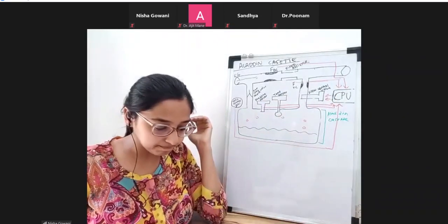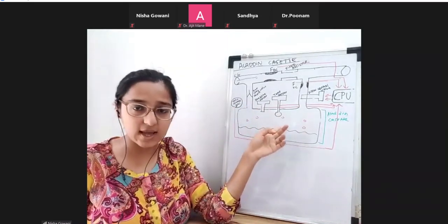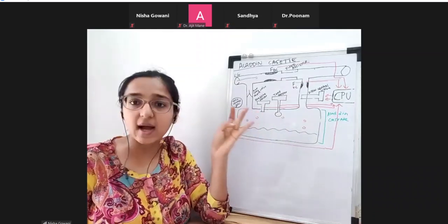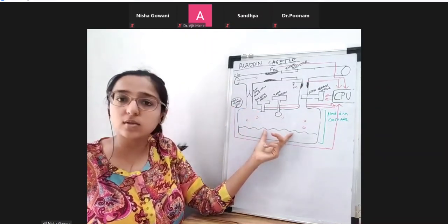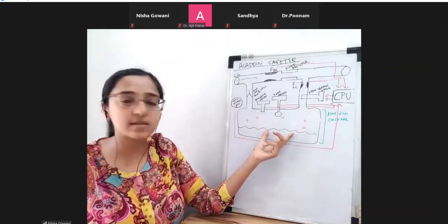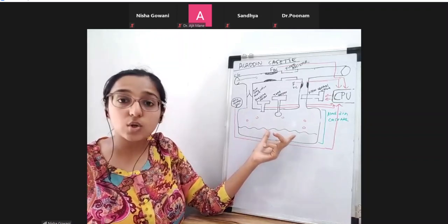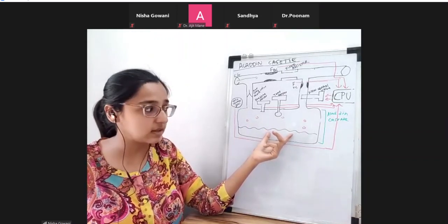So when you use a high flow rate through this Aladdin cassette, if high flow rates and high dial settings are used, a large amount of the liquid starts to vaporize. Obviously, a lot of evaporation means a lot of cooling, right? So you have to give external heat. From where will the external heat be provided?